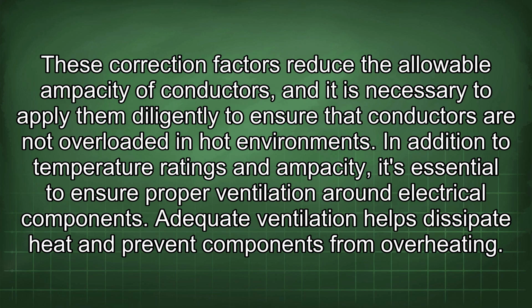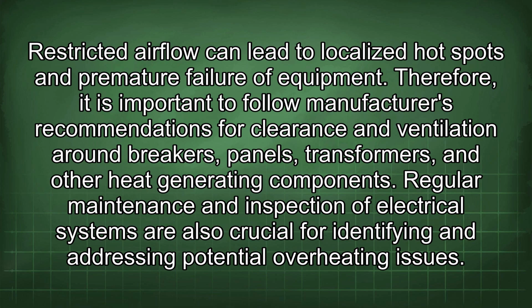In addition to temperature ratings and ampacity, it's essential to ensure proper ventilation around electrical components. Adequate ventilation helps dissipate heat and prevent components from overheating. Restricted airflow can lead to localized hot spots and premature failure of equipment. Therefore, it is important to follow manufacturers' recommendations for clearance and ventilation around breakers, panels, transformers, and other heat-generating components.